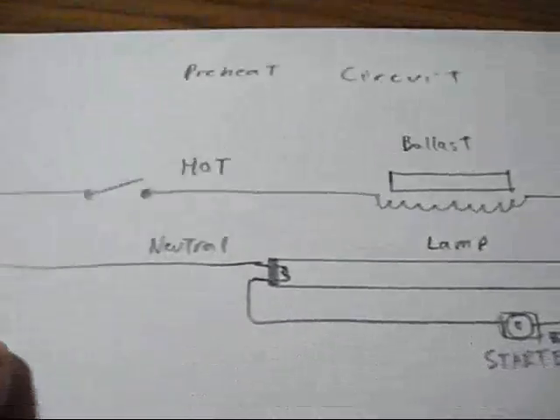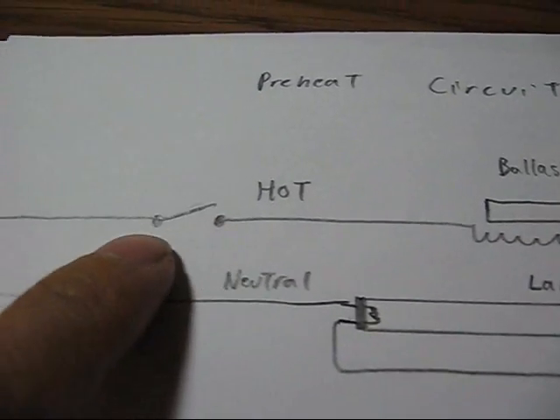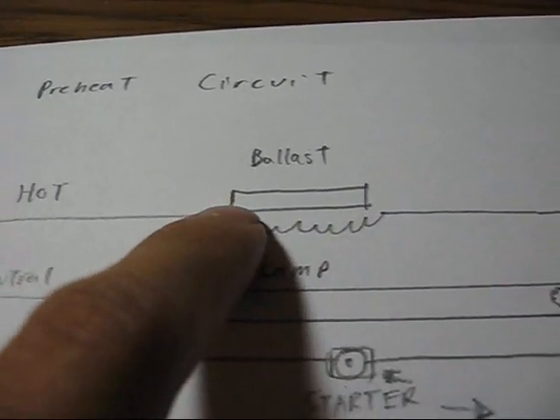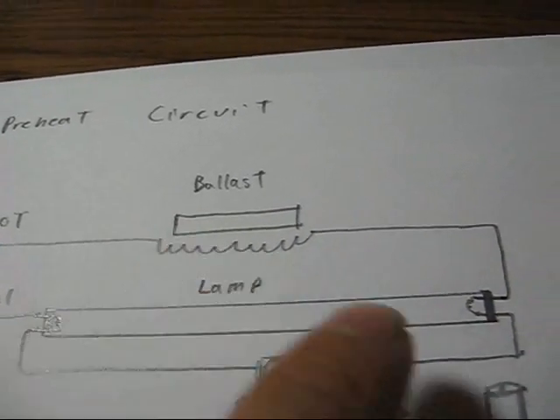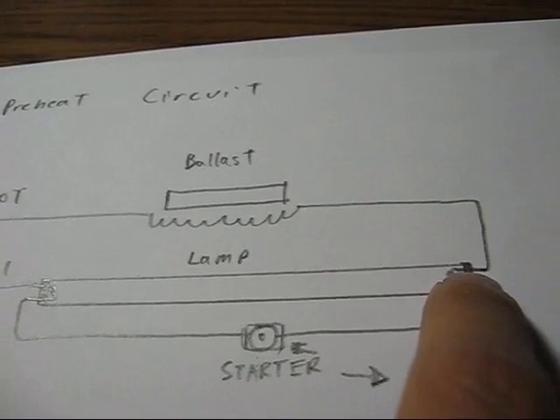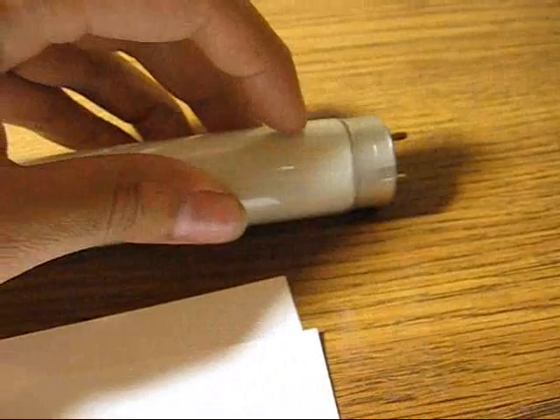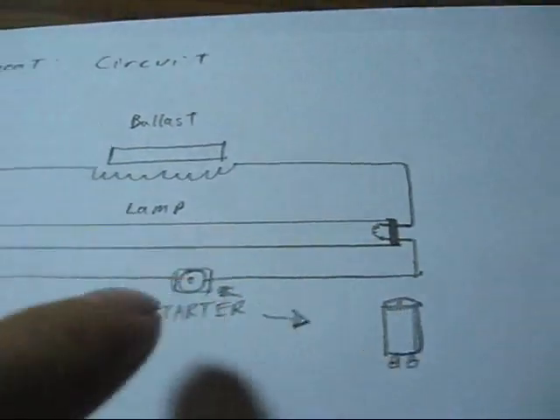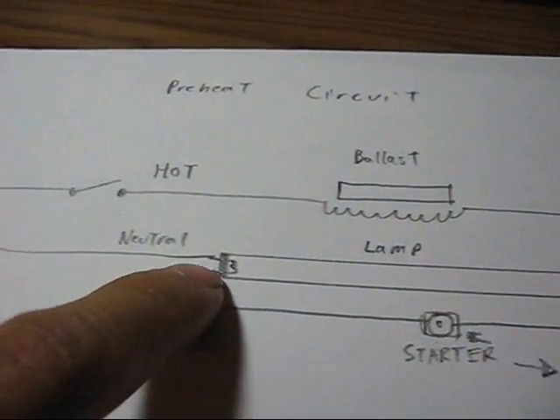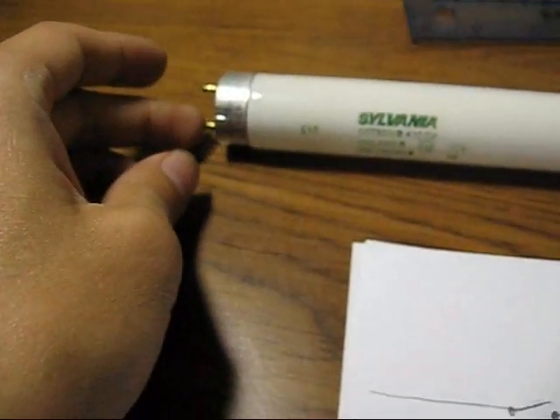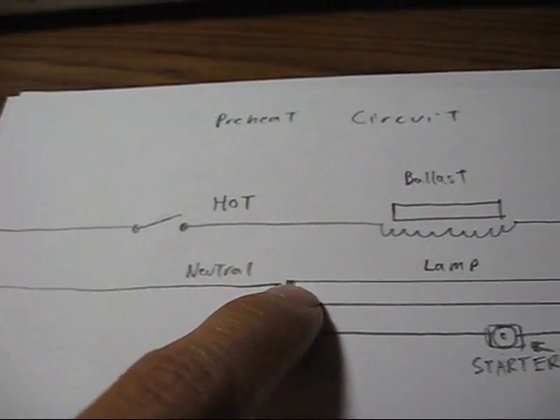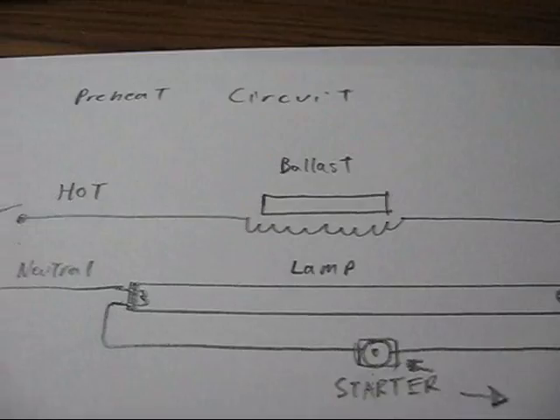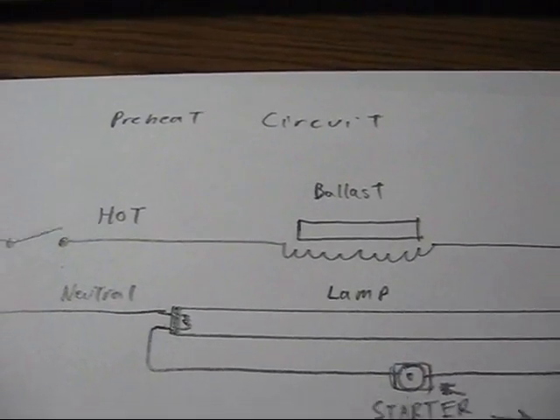Now let's take a look at your classic preheat start circuit. You have a hot wire coming in through a switch into the ballast, it's a simple choke coil in this case. Then you have it go through one pin on the end of the lamp, through the filament, and then out the other pin, through the starter, and then back into the other end, through the other filament, and then out to the neutral. That's your classic preheat start fluorescent lamp circuit.